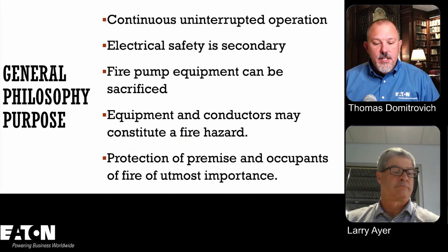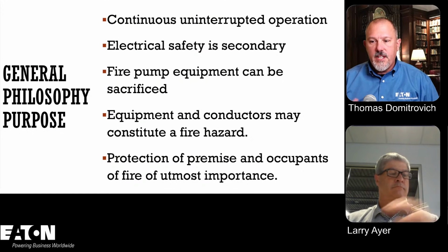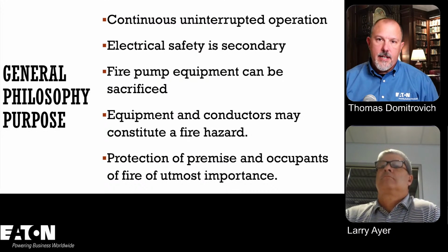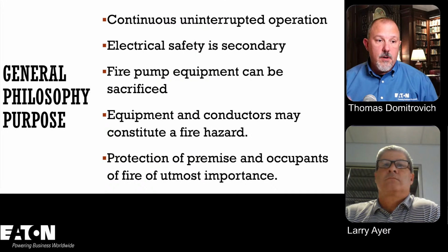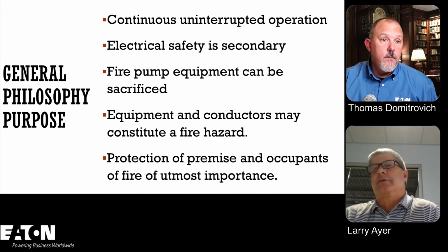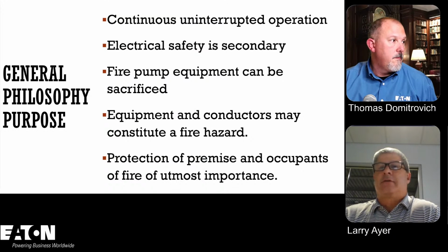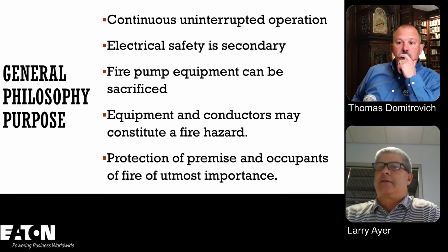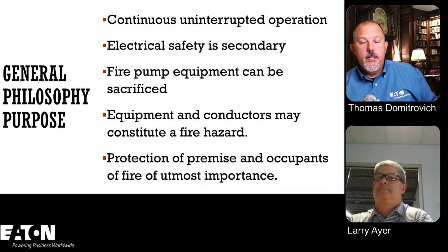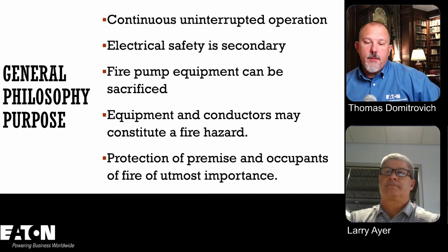Now, I think it's really interesting, Larry, from a safety perspective, I'm always worried about protecting motors, protecting conductors, protecting transformers. I would say this is probably the only part of the power distribution system that we want to run until it fails, no matter what, right? That's correct. One of the concerns is we want to make sure that we keep those fire pumps going and keep the sprinklers and the water trying to put out the fire. So we want to make sure that when all else fails, even if we have locked rotor conditions or whatever, we can keep that pump started and going and eliminate the fire hazard. Yep. And so the continuous uninterrupted operation is primary.